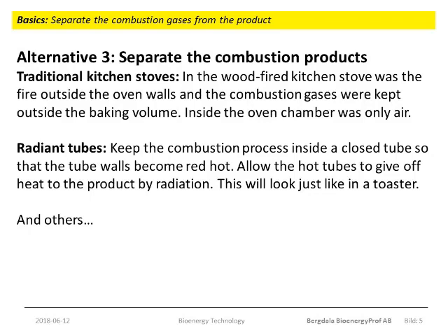A radiative tube is a tube inside which the flame and the hot combustion products are contained. The tube then becomes red hot and the tube transfers heat to the product by radiation, just like an electric heating element. In this case, the tubes are exposed to very high temperatures and high gas velocities from the inside, and the corrosion resistance of the tube material becomes crucial to the lifetime of the installation. The last option, heating from outside or heating by radiative tubes, also opens up for the use of any specific atmosphere in the process chamber.